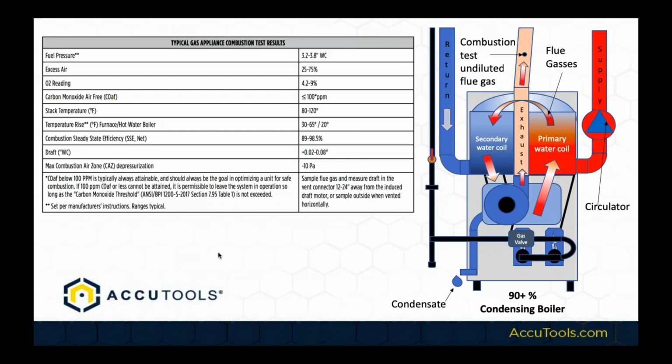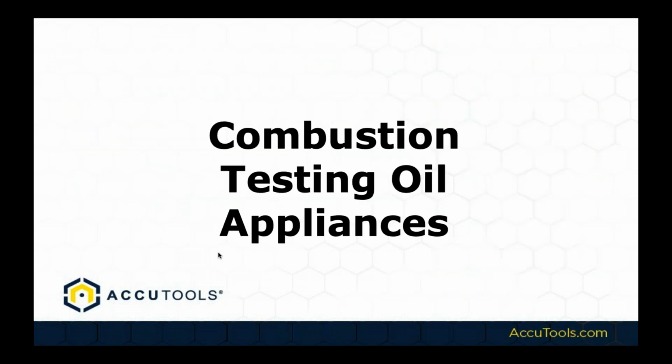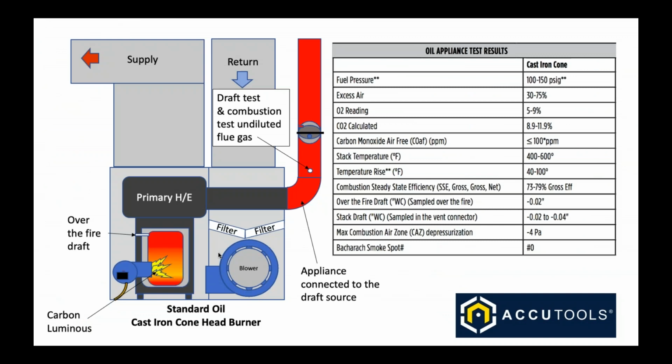Canada, you've got to be careful. You guys have different venting requirements as far as the materials that are used, but make sure that we're paying close attention to the stack temperatures on there, and paying very close attention to the temperature rise across the boiler. K-type thermocouple clamps can be used, or you can use B-type thermocouples with your BluFlame analyzer, differential temperature across the boiler. It's really the only tool you really need to get this thing set up properly.